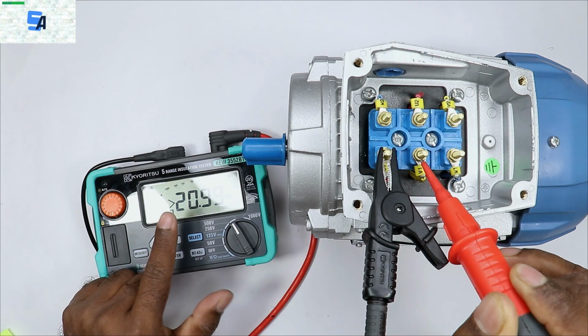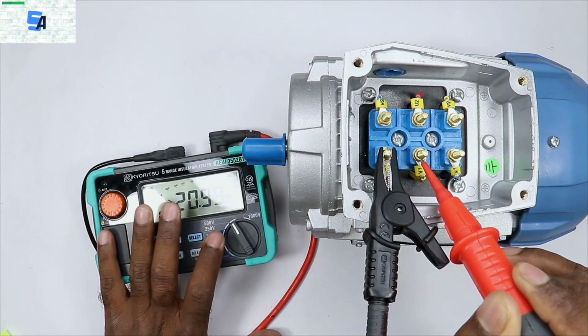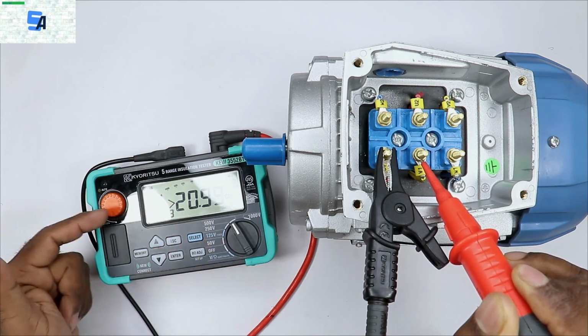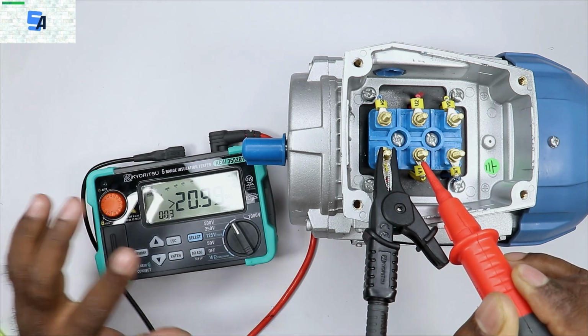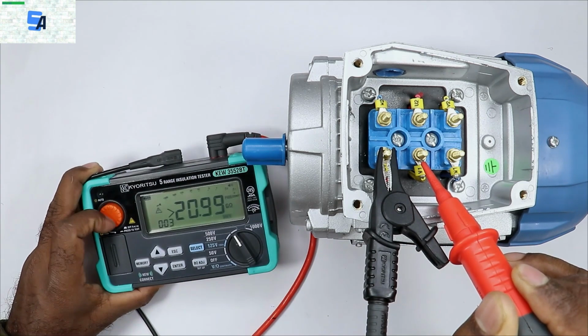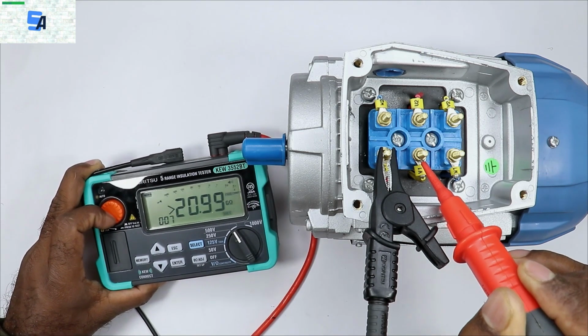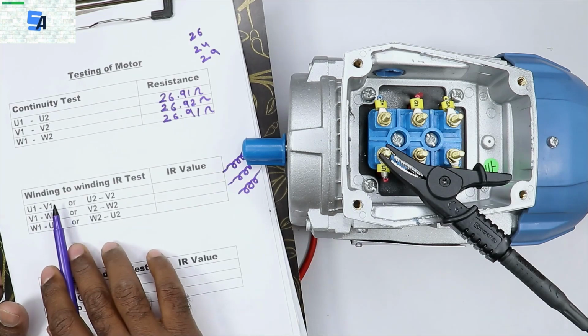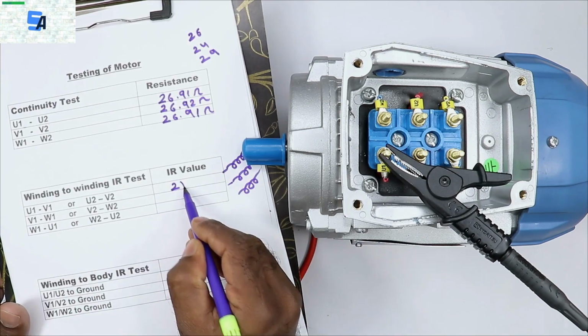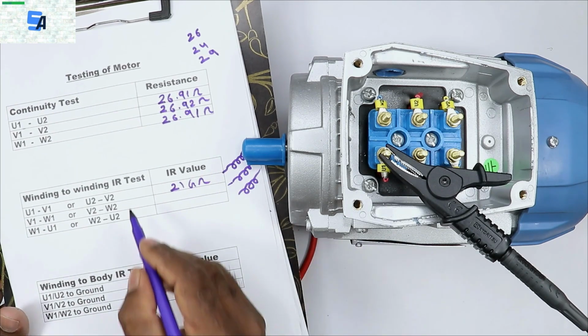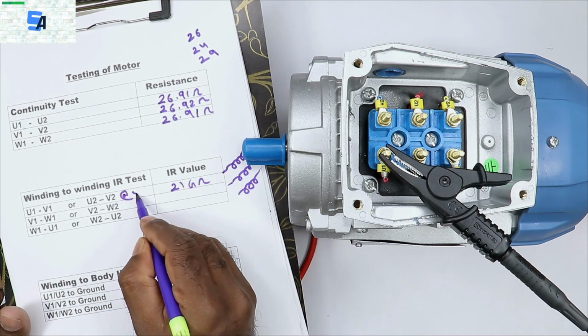In some meggers, it shows OL. Whether it is OL or the maximum value, it is the same thing. So for now, between these 2 windings, we are getting an IR value of 20.99 giga ohm. We can say 21 giga ohm also. So right now between U1 and V1, we are getting a 21 giga ohm IR value. And we are using 500 volts here for measuring the IR value.